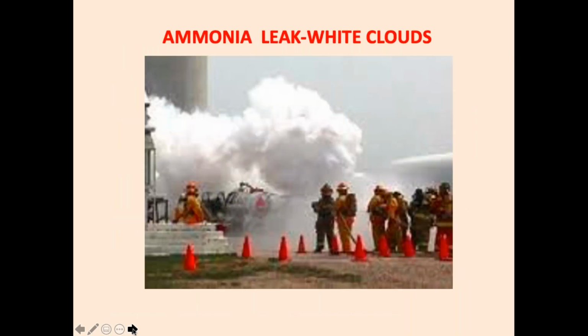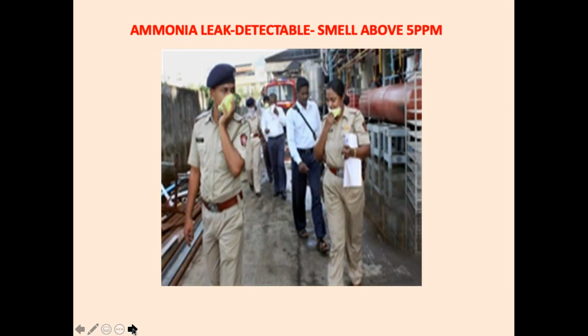This is what happens when ammonia leaks. A white cloud is formed in the machine room or outside because the atmosphere has moisture content and the ammonia easily gets absorbed into the moisture. A white cloud is normal in winter or in monsoon, and similar clouds are seen when ammonia starts leaking. Ammonia can be detected with smell.